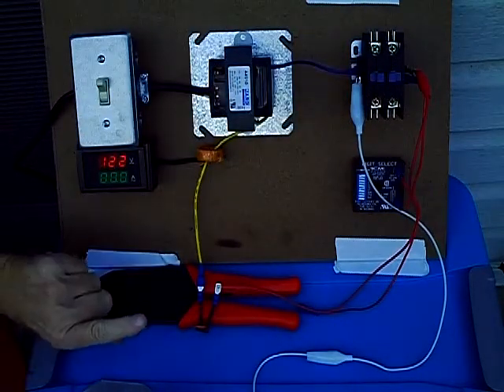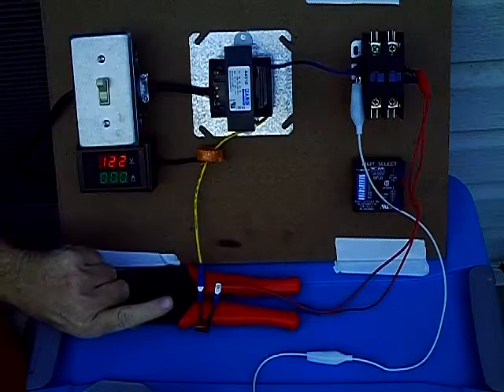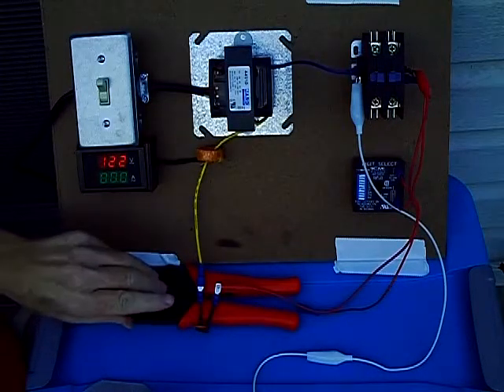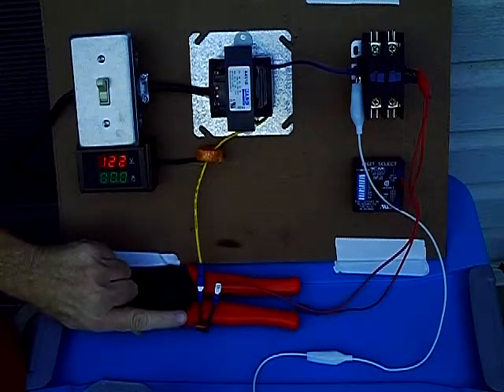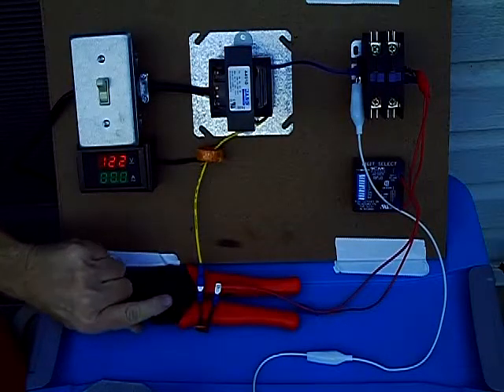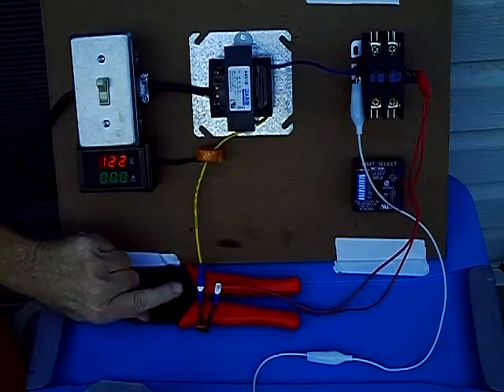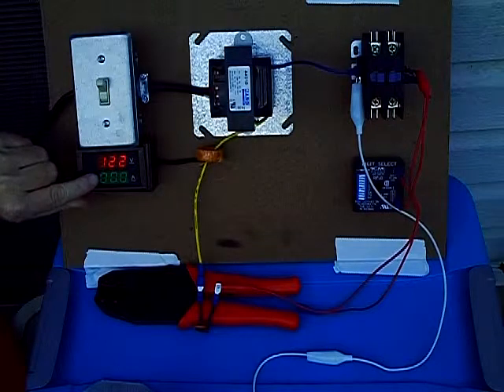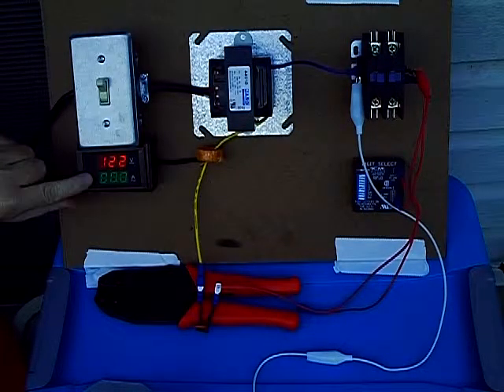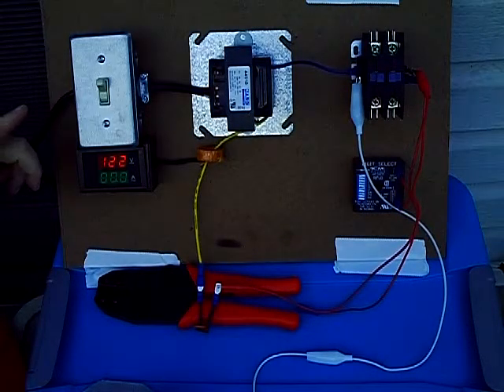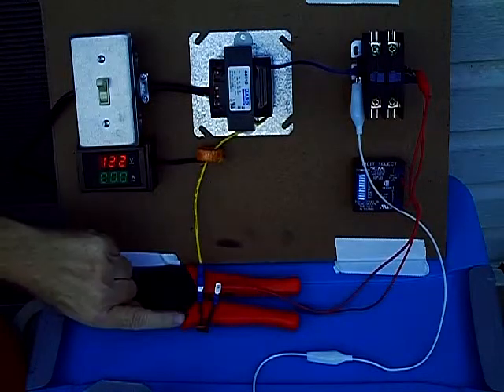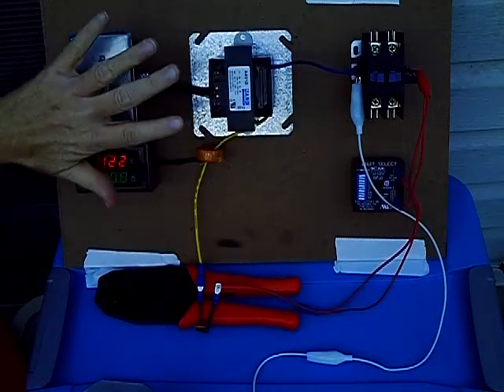Now right now we're tripped, and unlike the Short Pro tool, this doesn't have a little LED light to show you that it's tripped and protecting all the circuits. One thing you can do is, if you have your amp probe on, you'll see it's all zeroed out here. There's no current going across there. It's opened up and it's protecting everything.